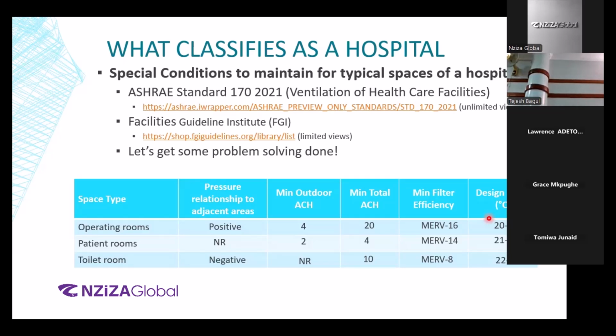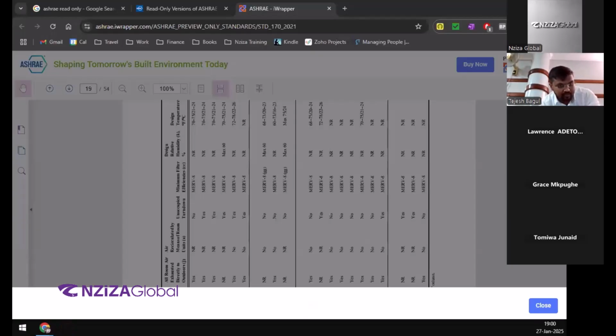So again, as I said, when you have an air handling unit, let's talk about a general air handling unit, not just for the hospitals, right? You have a supply stream, right? That supply stream, if you check, has ventilation air or outside air, right? So that supply air comprises the total minimum ACH, as well as the component of the outdoor ACH, right? I'll show you a schematic. This is a bit ahead in this thing.